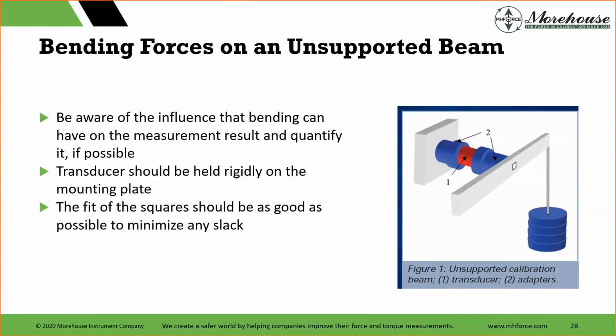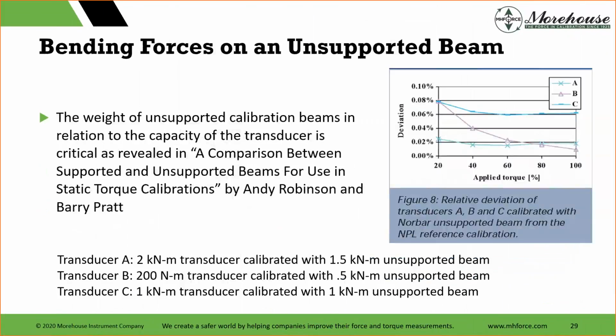And here we have an unsupported beam. You see the weights, you see the transducer. They say, be aware of the influence that bending can have on the measurement result and quantify it if possible. Again, transducer should be held rigidly on the mounting plate. The fit of the squares should be as good as possible to minimize any slack. And here's what they did. They took 3 beams and 3 transducers, and they have a transducer ABC, 2 kilonewton meter calibrated with a 1.5 kilonewton meter unsupported beam, a 200 newton meter calibrated with a 0.5 kilonewton meter unsupported beam, a 1 kilonewton meter transducer calibrated with a 1 kilonewton meter unsupported beam.